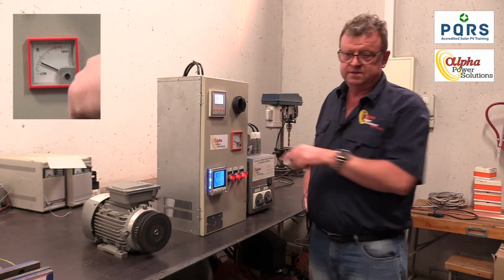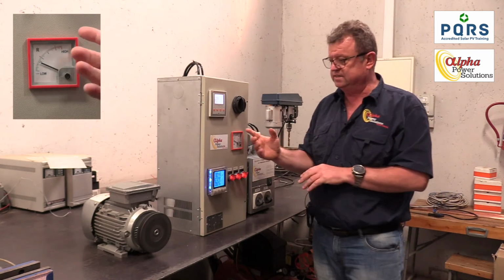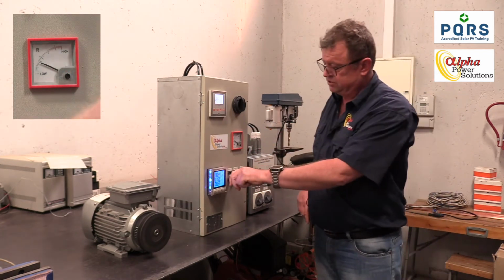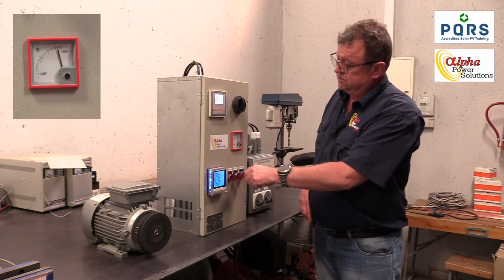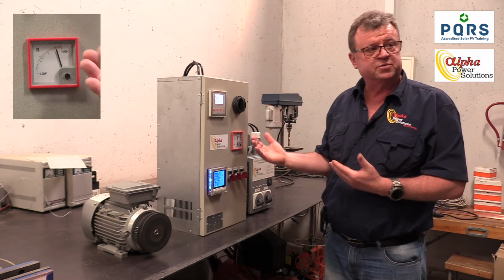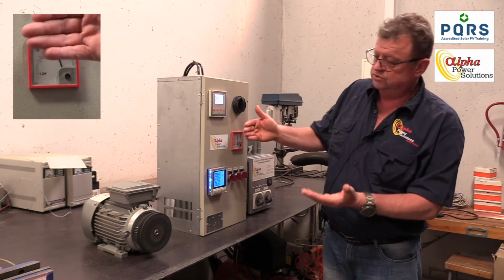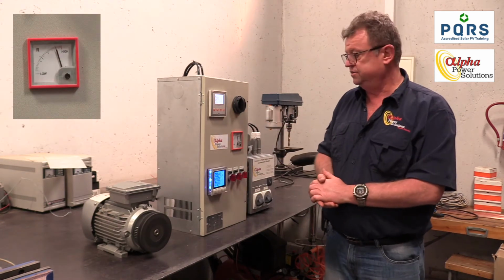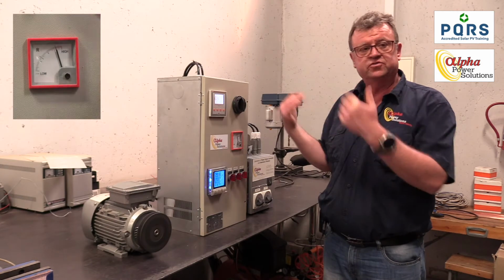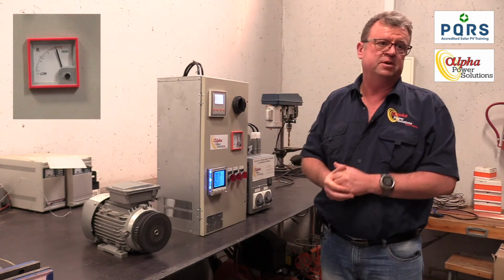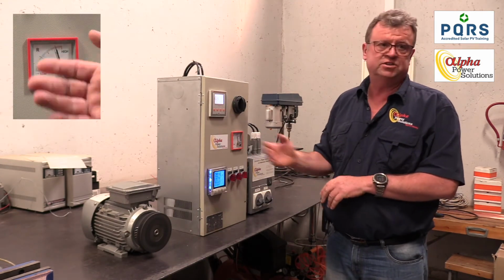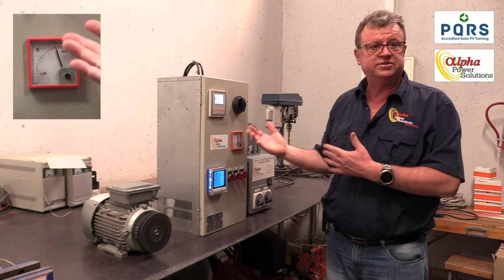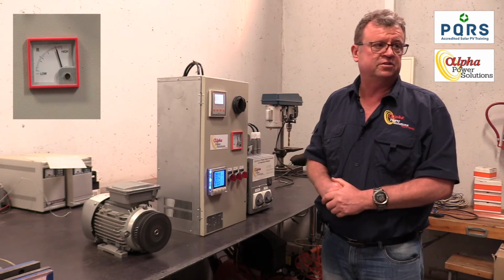This little meter I've introduced so you can see that if the power factor correction is off, the cost to run the motor is pretty high. But as you reduce the reactive load being drawn from the grid, obviously you pay much less. So it's a representation of the cost reduction that you get when you put power factor correction in.